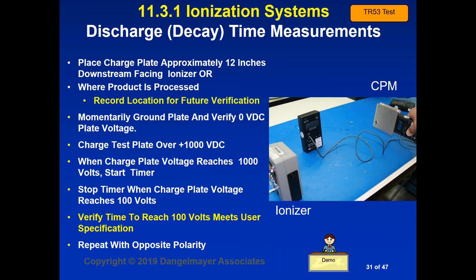What you see in the picture, you have the ionizer on the left, you have the handheld instrument on the right, and in between is the timer that is going to turn on and off at 1,000 and 100 volts. Once you've done the measurement for one polarity, you do have to repeat it for the other polarity because there's no guarantee that your ionizer is working for both polarities. You have to check every ionizer for its neutralization or discharge time for both polarities.